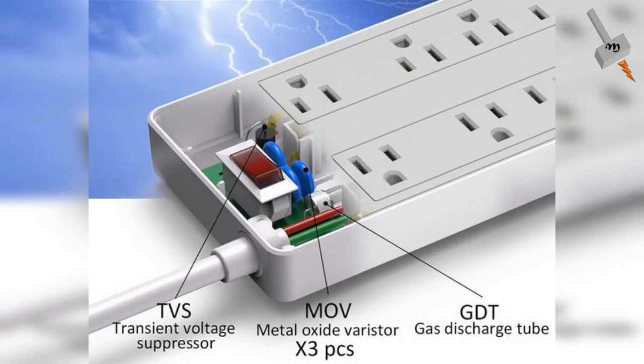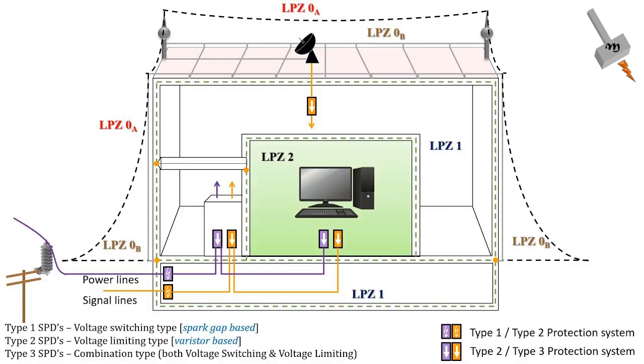Apart from the above-mentioned methods of electromagnetic shielding, surge protection devices can be deployed to remove the interfering signals. The different types of protection devices are transient voltage surge suppressors, gas discharge tubes, or MOV-based surge suppressors. The system is designed with different zones of protection to improve reliability.